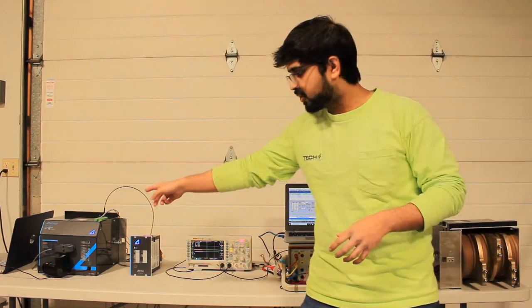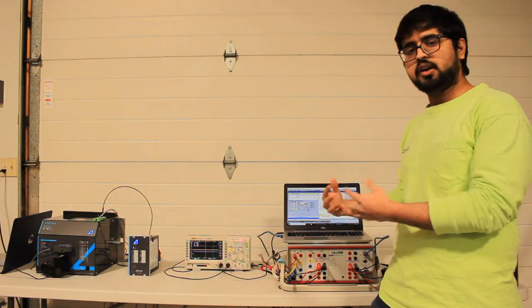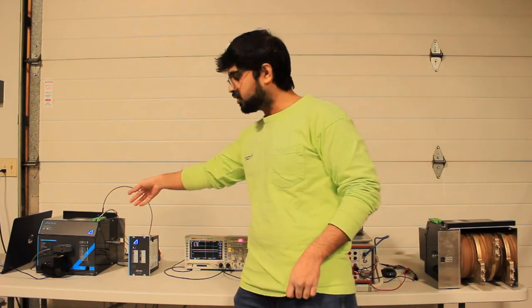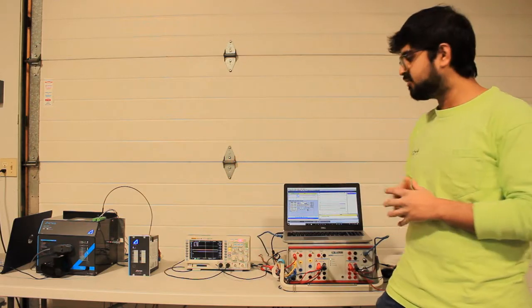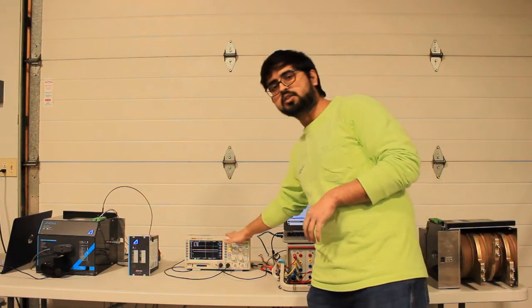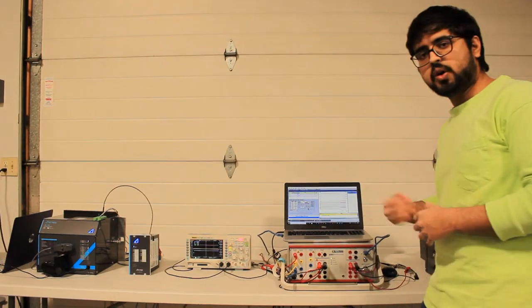What's going to happen here is when I run the state sequence, the Ponovo test kit is going to inject current into the arc flash protection relay, and at the same time the flash is going to be triggered. So when there's light plus current input, the AQ-110 relay is going to trip and send a trip signal to the quencher, and the quencher is going to go off. All of this is going to happen under five milliseconds, and you can verify here with the oscilloscope.